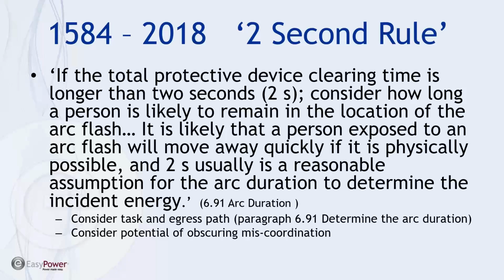If the total protective device clearing time is longer than 2 seconds, consider how long a person is likely to remain in the location of an arc flash. If it's likely that a person exposed to arc flash will move away as quickly as possible, 2 seconds is usually a reasonable assumption for the arc duration used to determine the incident energy. In other words, what they're suggesting is if I have the ability to move once an arc starts, then it's reasonable to limit the calculation time for incident energy to 2 seconds. And they go on to say you need to apply engineering judgment before applying this rule.